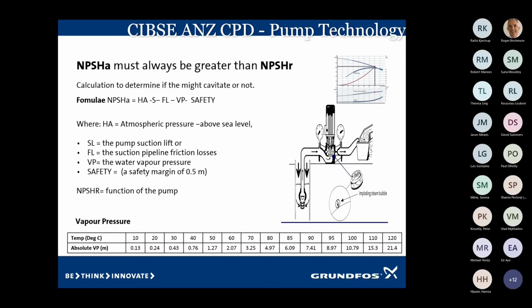So going to the calculation, we have our net positive suction head available, which is atmospheric pressure. And I always work on 10 meters, even though it's slightly greater. So you're starting off with 10 meters. From that point, we have to take off the suction lift, which is, as we know, from the water level sitting in the well to the center line of the pump. So we take off the suction lift.